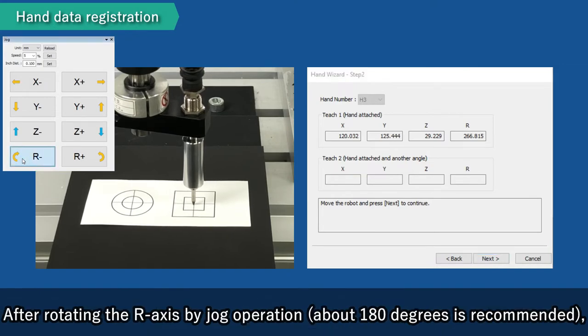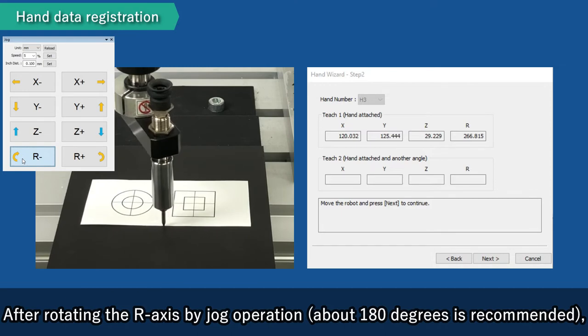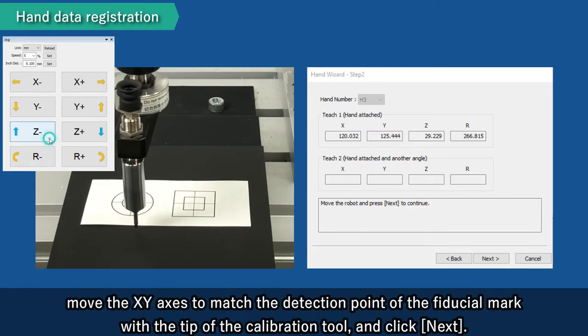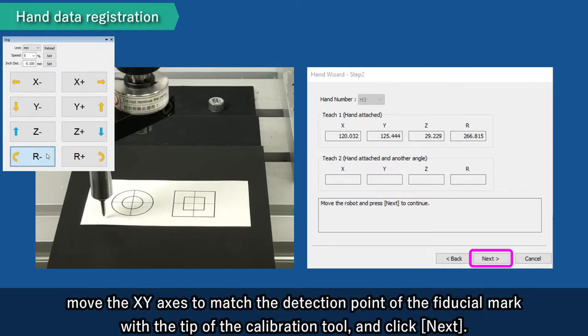After rotating the R-axis by jog operation, move the XY-axis to match the detection point of the fiducial mark with the tip of the calibration tool and click Next.